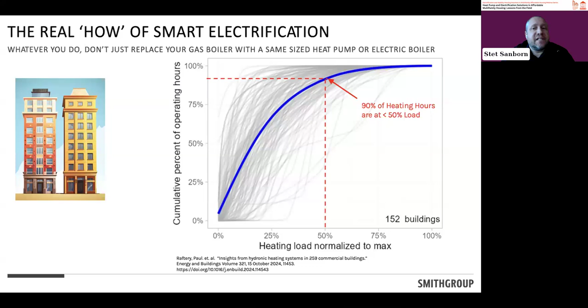And so you can put a hybrid together where maybe you use heat pumps to cover that 90% condition, but leave your boiler in place to cover a peak day, peak event, or those cold snaps, the Arctic blasts that come down and sit there for 2 weeks. A hybrid solution is not a horrible solution to meet your decarbonization goals, because that boiler is almost never going to run 90% of the year. It's just the heat pump and then the boiler's there just in case.